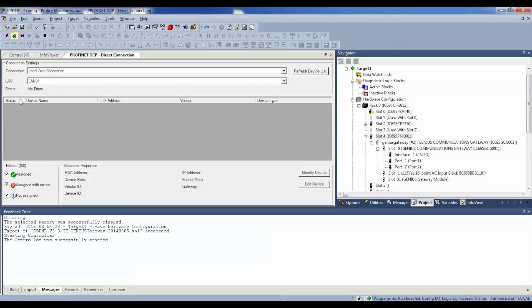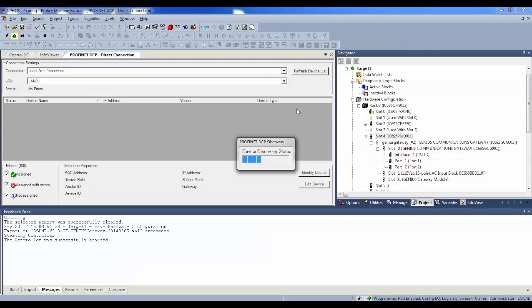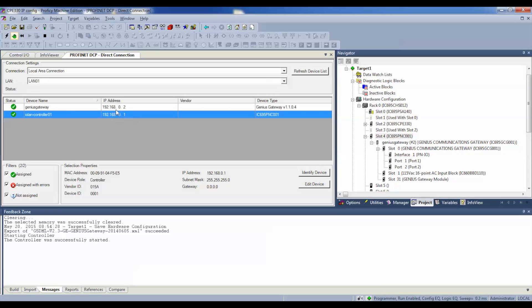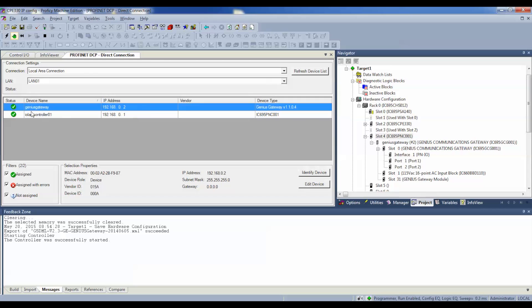So, what we'll do is refresh our device list. And, it's going to go through and see if it can find our GCG and Profinet controller. Okay. So, it's showing us that it has these controllers and it's showing us the IP addresses that were established to them. Now, of course, I'm just using the default addresses on these. But, it shows you that these two, the status is that they're assigned and they're communicating with each other. And that's what you want to see.